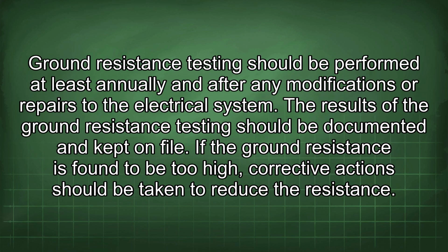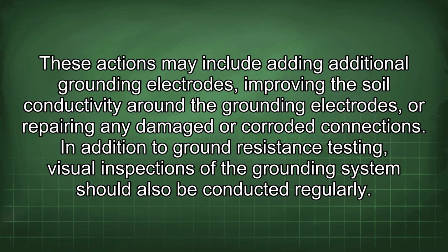Ground resistance testing should be performed at least annually and after any modifications or repairs to the electrical system. The results of the ground resistance testing should be documented and kept on file. If the ground resistance is found to be too high, corrective action should be taken to reduce the resistance.